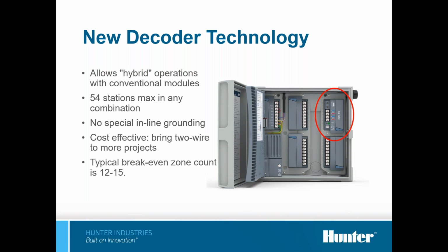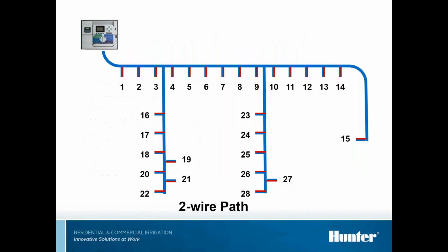So you can bring 2-wire into a lot of projects. This is more catered to smaller projects where you're not going to be going far distances. Your typical break-even count is going to be about 12 to 15 zones. All right, going back to the decoders. Here's your controller. And let's say you take your 24-volt power supply.